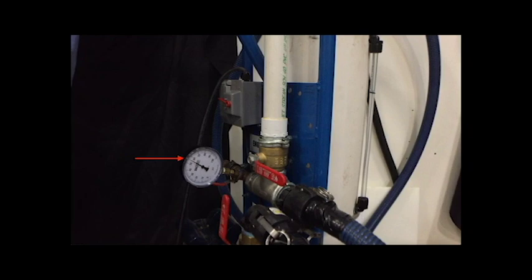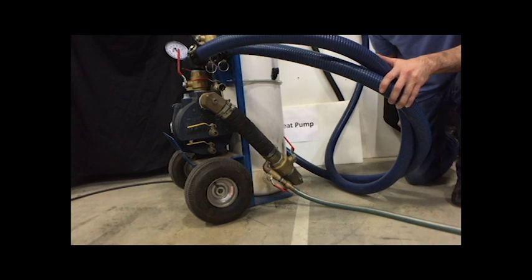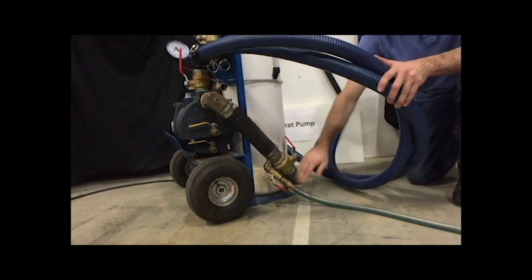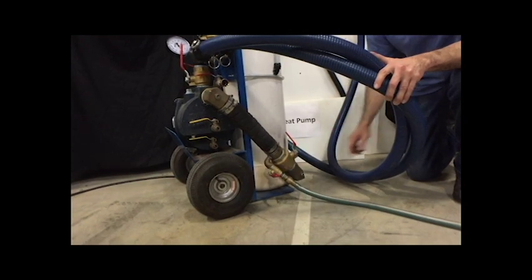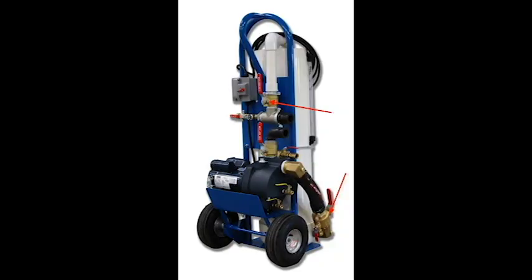Monitor the pressure after deadheading. It will quickly climb to 80 to 100 PSIG. When the pressure reaches 80 to 100 PSIG, close the half inch fill valve. Then open the inch and a half deadhead valve and the two inch tank isolation valve simultaneously.